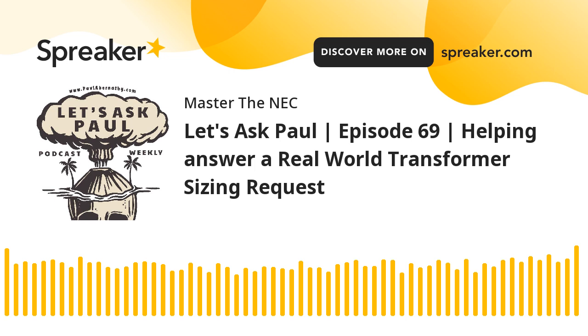Okay, so more often than not, and you know this as well as I do, when people are installing air conditioning units, they look at minimum circuit ampacity, maximum overcurrent protection. They always go to the max. They just always do. So you don't have to go to the max. That's the maximum overcurrent protection. But since the manufacturer gave you this, there's this probability maybe that it won't hold. I don't know. But we're going to go with the premise this is what they give you. So in this case, it's 78 amps.